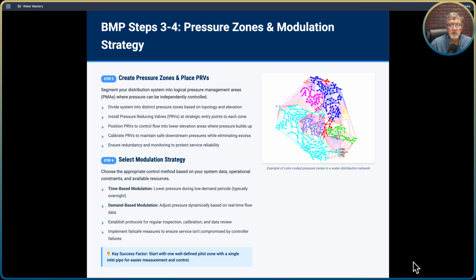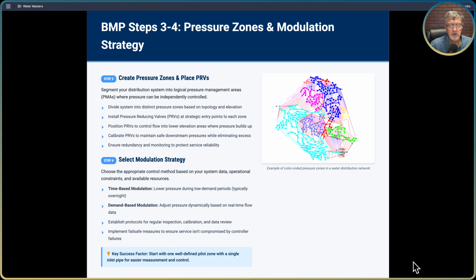Steps 3 to 4, pressure zones and modulation strategy: creating pressure zones and placing the PRVs, the pressure reduction valves, or pressure regulation valves. I think it's better called pressure regulation valves because you may adjust the pressure up. If you have automatic ones, you're going to adjust the pressure up during the day and lower it at night. So I think it's better calling it a pressure regulation valve. But that's just my little quirk here.